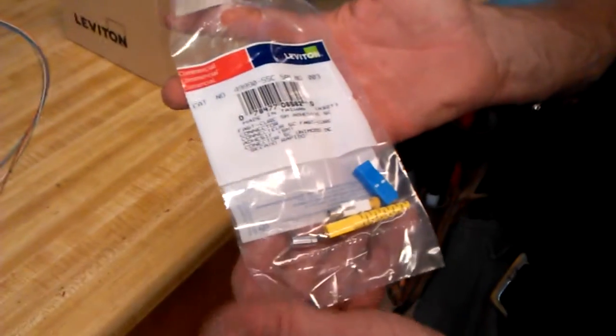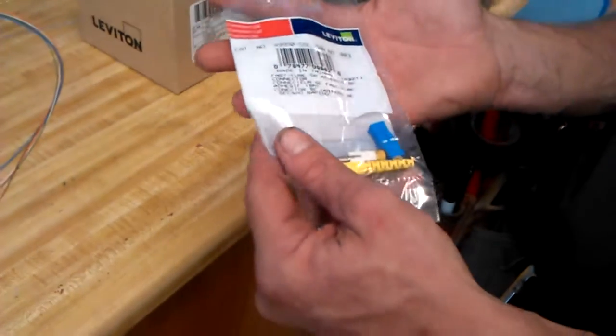Alright, so the next step here is terminating the fiber optics. What we're going to be working with here is a Leviton product that I showed up with on the job site. This is an anaerobic type connector, which means it's a binary type glue. Here's the glue, the Loctite 680 that we're going to be using.